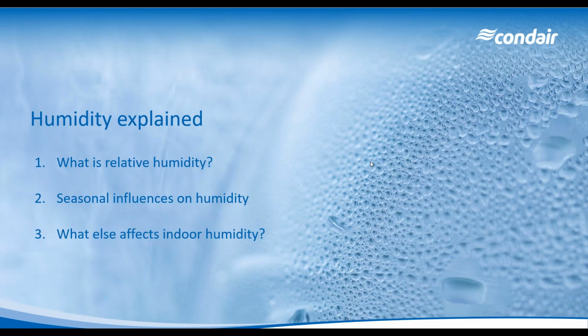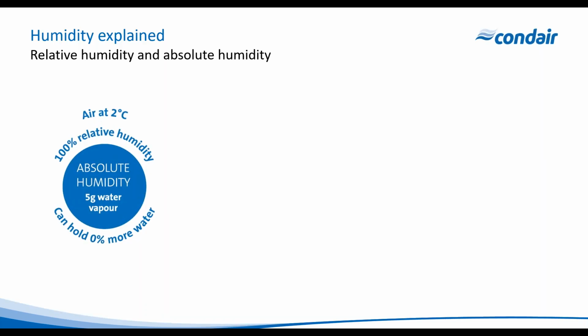So let's start by looking at explaining humidity. What is relative humidity? What seasonal influences are on humidity, and what else affects indoor humidity? So on this slide, you can see we've got a blue dot, and that blue dot represents 5 grams of water vapor in air at 2 degrees C. So at 2 degrees C, 1 cubic meter of air with 5 grams of water in the air is completely saturated. It can't hold any more water.